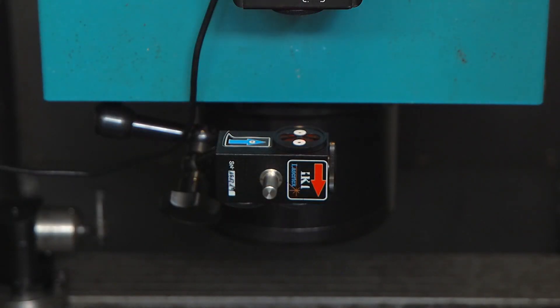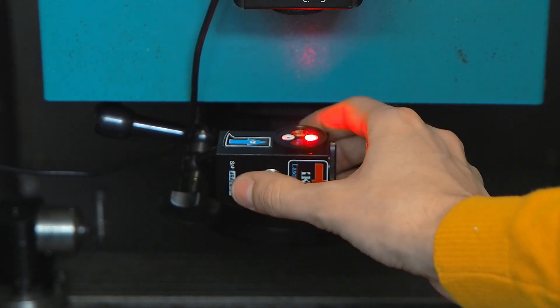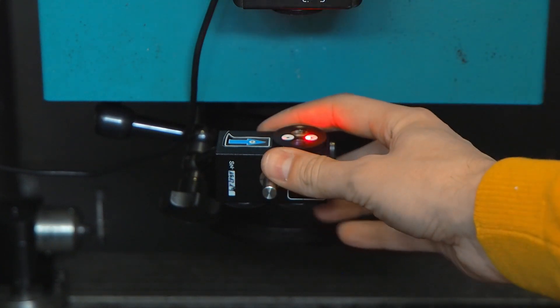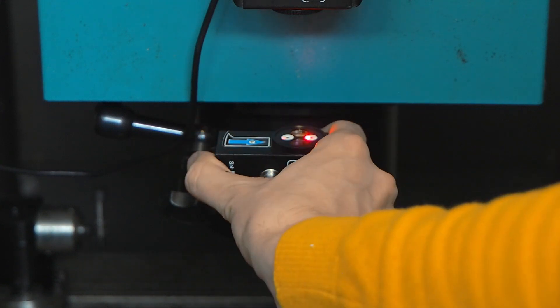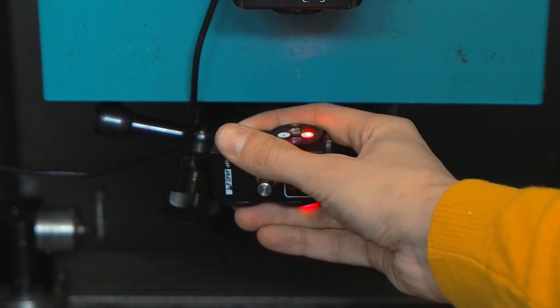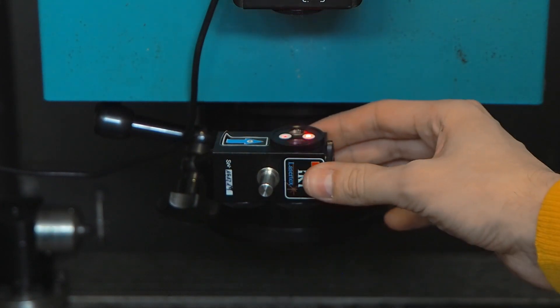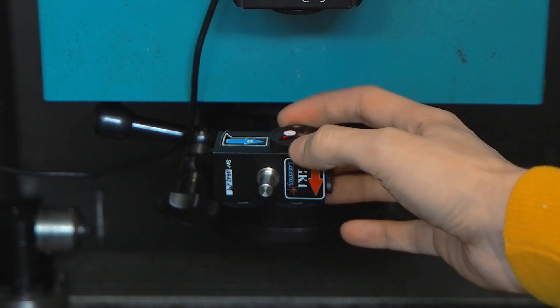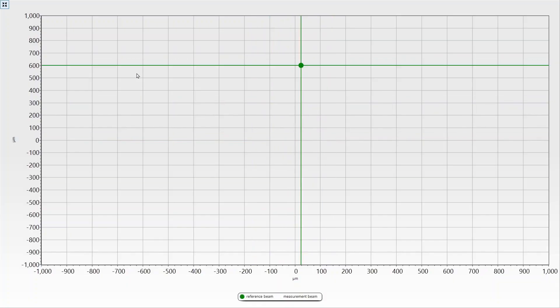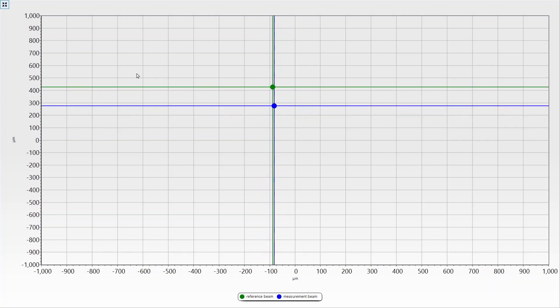The alignment procedure is basically the same as it was with the reflector. Roughly align it with closed apertures until you see the reflection in the second aperture. When you do see the reflection, open the aperture and align it with your hand while looking at the screen of your software. The beam should be close together and as close to zero as possible. Try to align one axis at a time — it takes time to practice.